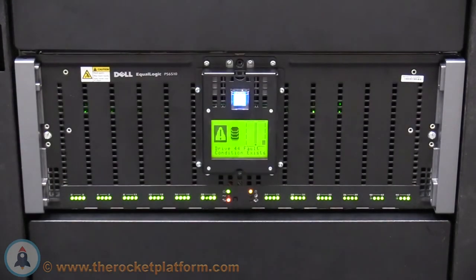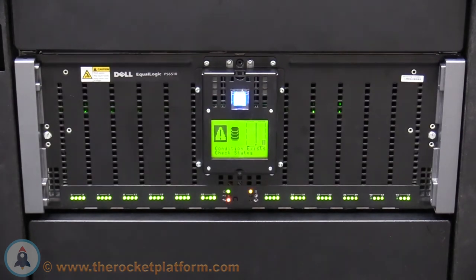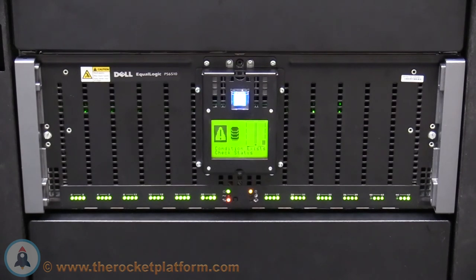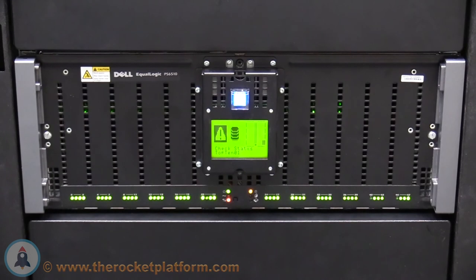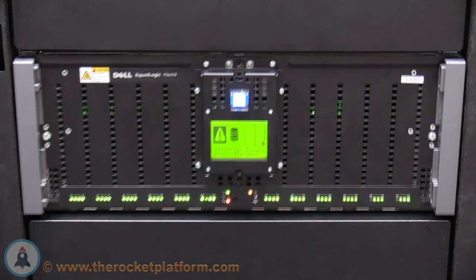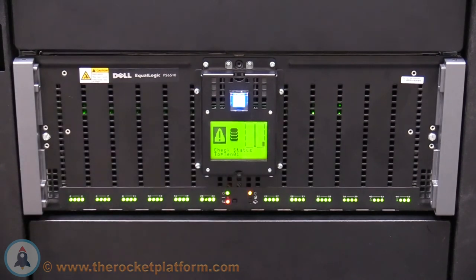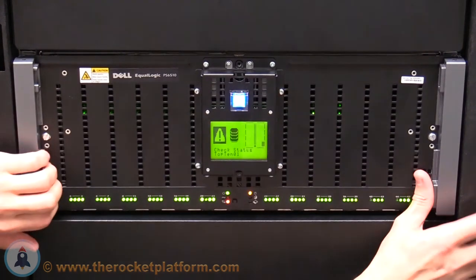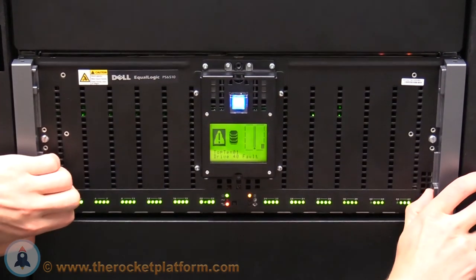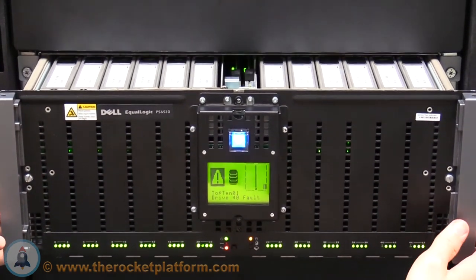Now from the front of the EqualLogic Array, you are able to see that the drives in slot 40 and 44 have failed. You can verify this by the LED indication that will be showing on the LED screen. Once you can confirm that these are the drives that will need to be replaced, you will need to confirm that the cabling has enough slack for you to slide the enclosure forward to access the failed drives. Slide the enclosure forward until you can readily access the faulty drive.